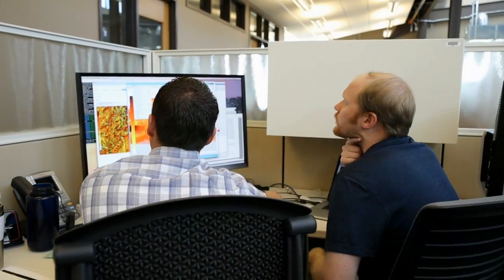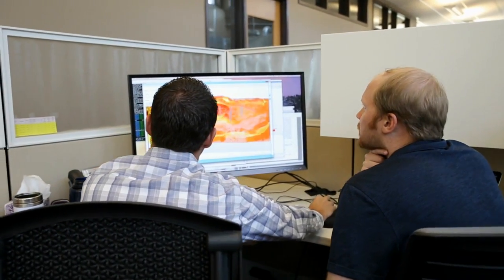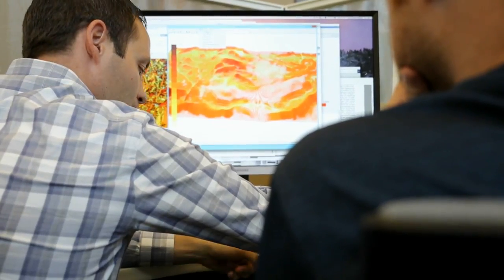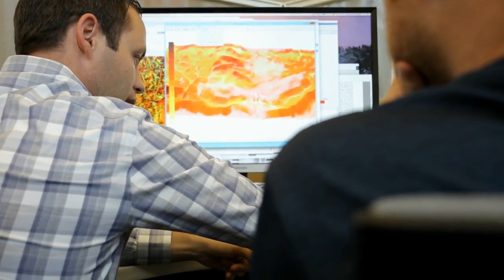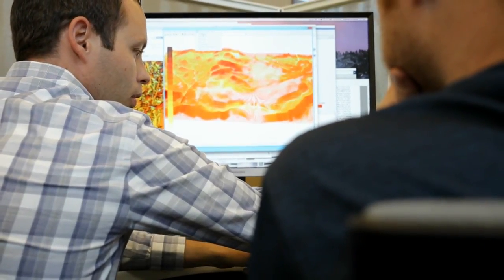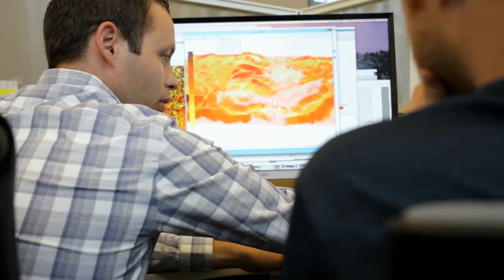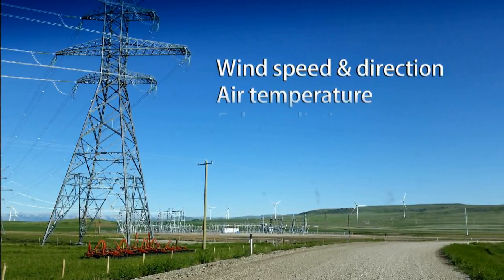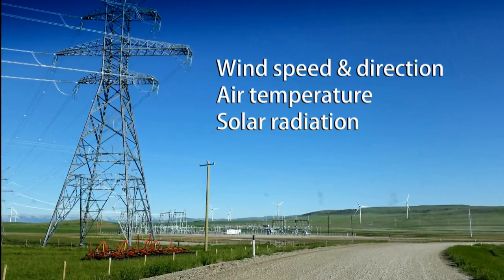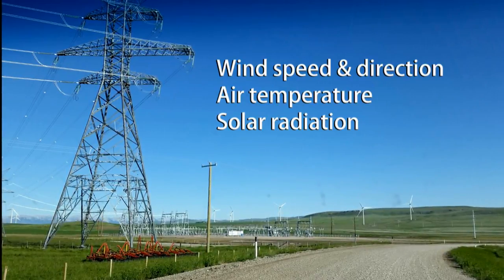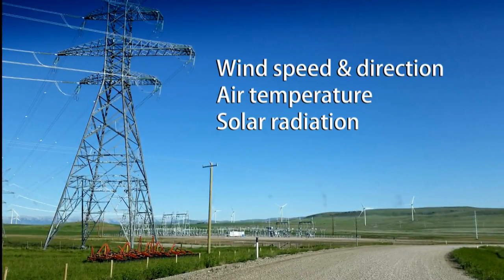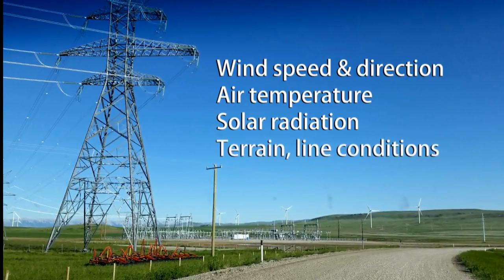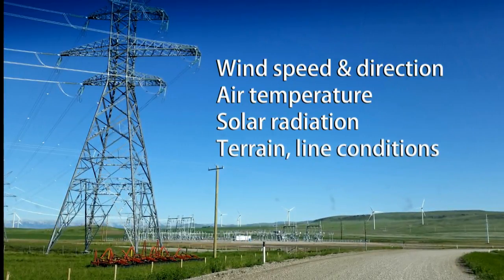A software application called GLASS combines power flow and weather information to give utilities user-friendly access to accurate, real-time assessments of dynamic line limitations. It accounts for dynamics such as wind speed and direction, ambient air temperature, and solar radiation exposure, all of which affect the relationship between current and temperature. It also factors in variables such as terrain.